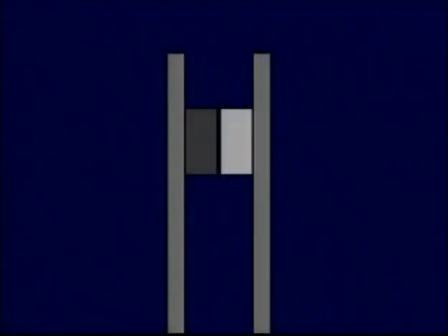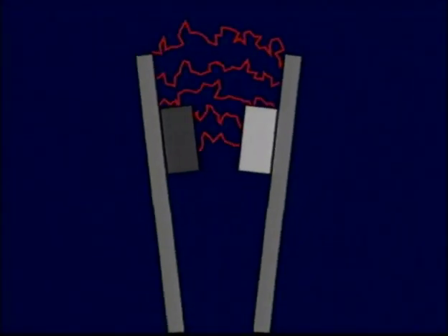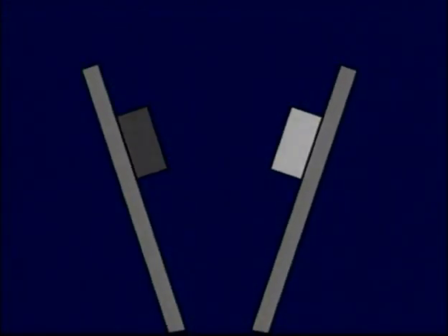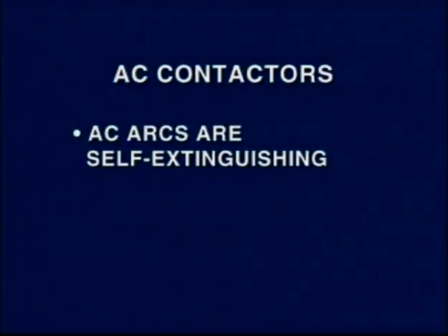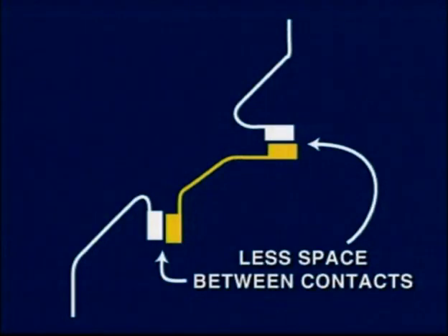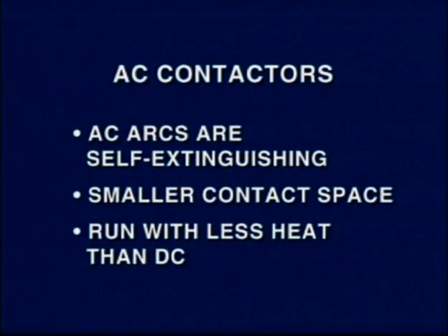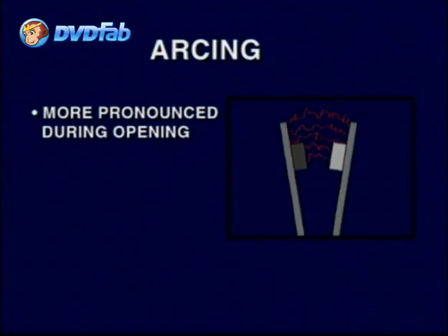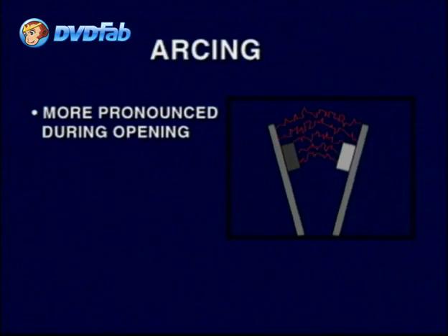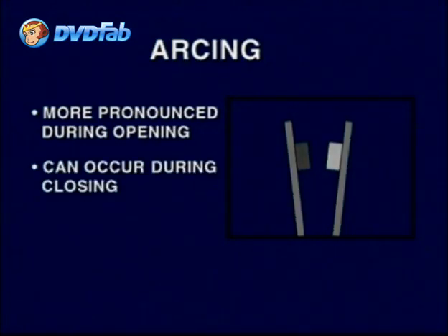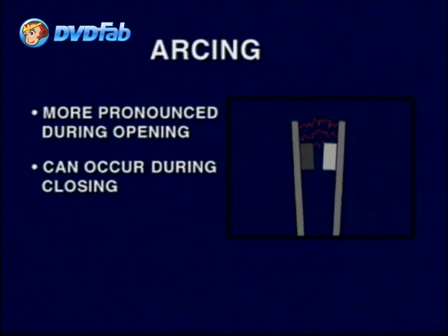The DC arc will last until the two contacts are so far apart that the arc extinguishes itself, and therefore there is more gap in between the two contacts. In contrast, AC arcs are self-extinguishing, thus having smaller space between the contacts. So AC contactors tend to run with less heat than DC contactors and have an increased contact life. Arcing is much more pronounced during the opening of the contacts because current is already flowing through the contacts, although it can also occur during the closing of contacts.